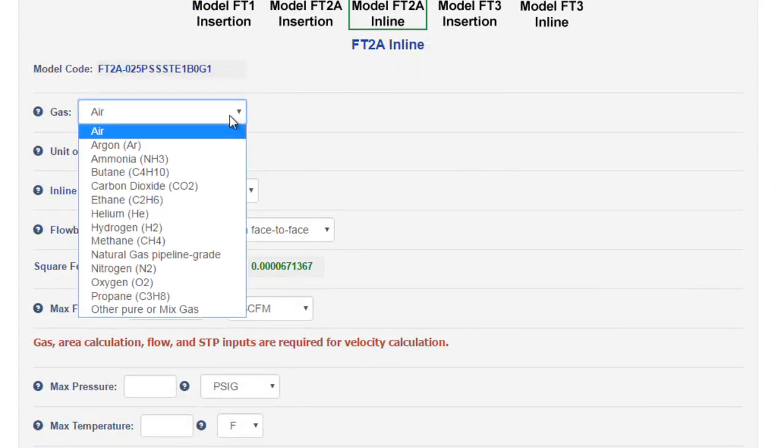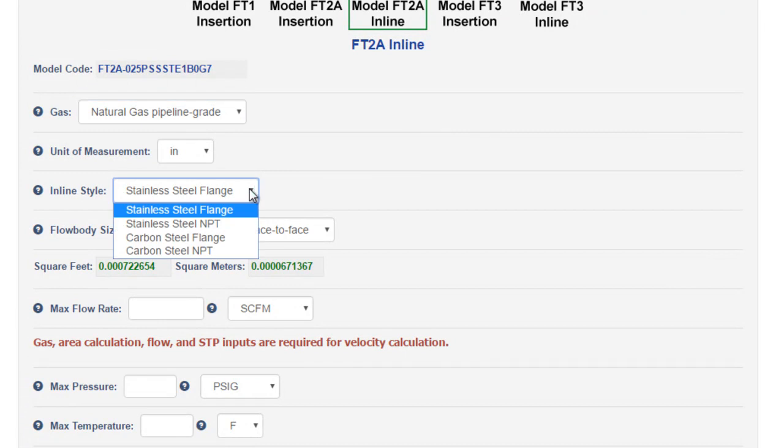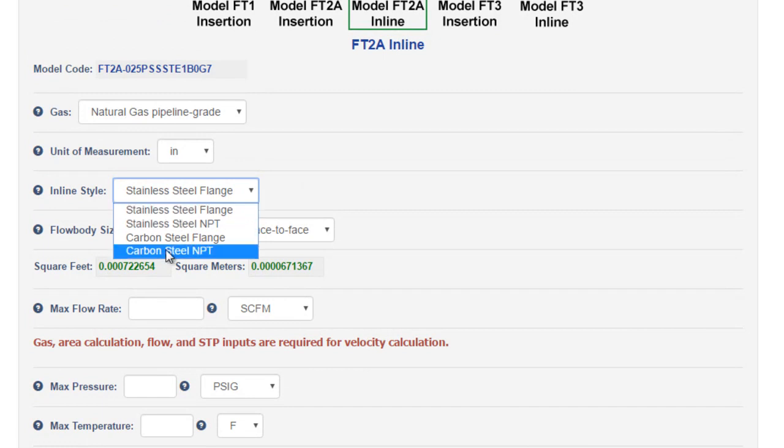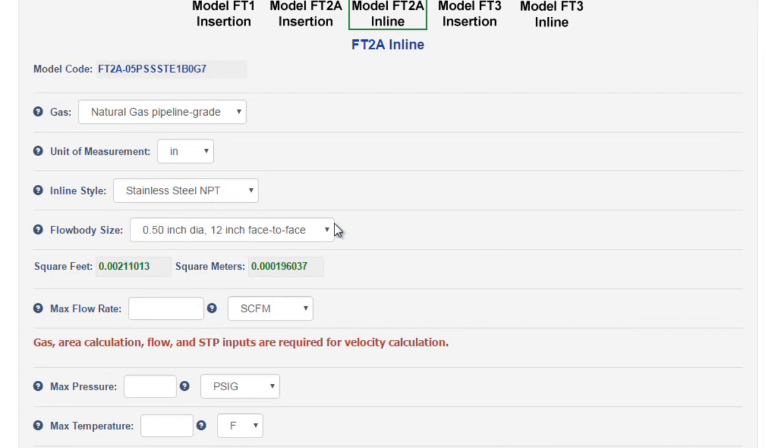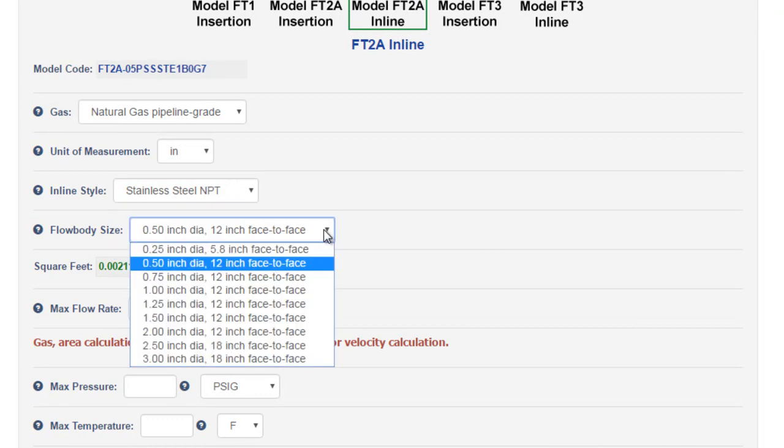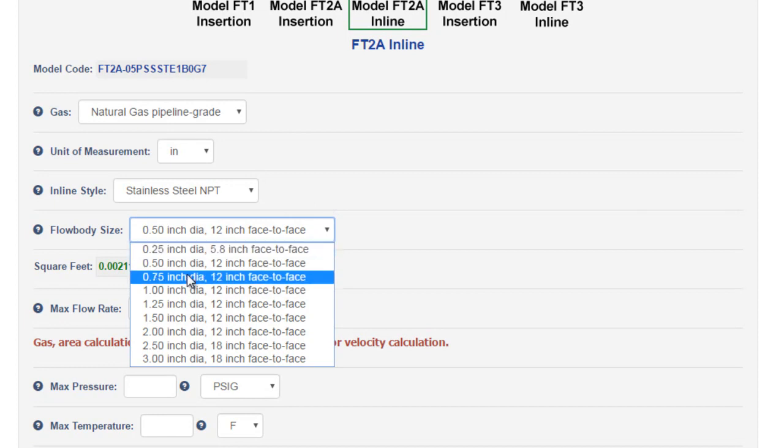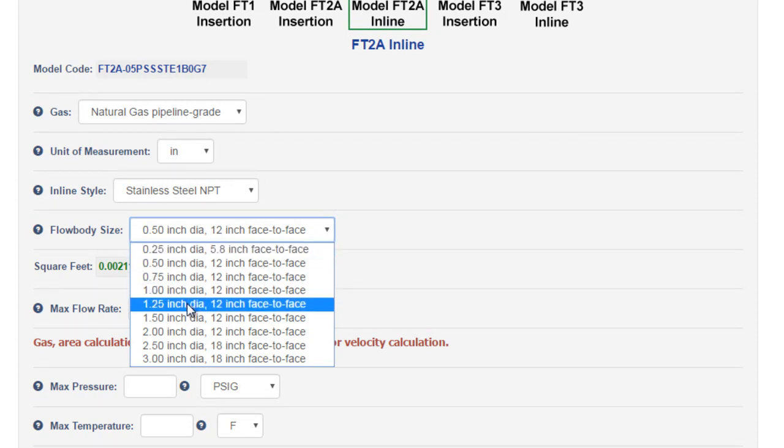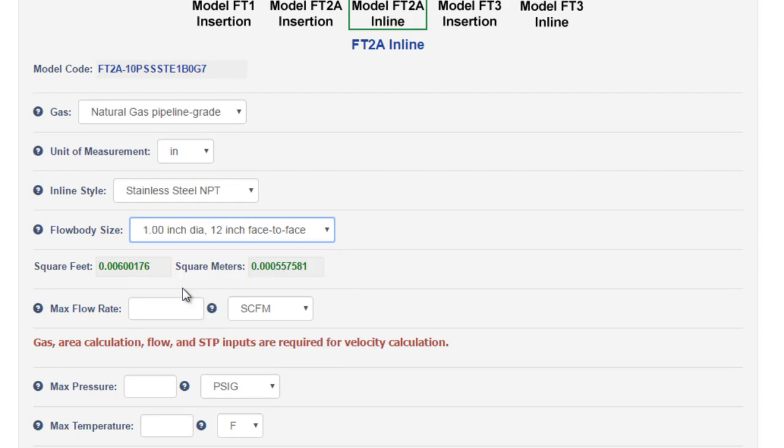This time we'll choose natural gas. We'll leave the units of measurement in inches, and then we'll choose between our process connections on the flow body. In addition to flange versus NPT, you can also choose between stainless steel and carbon steel for most pipe sizes. Let's go with stainless NPT. The flow body size is next. You'll note that the smallest pipe sizes are only available for inline meters. Quarter inch, half inch, three quarter, one inch, and one and a quarter. Let's do a one inch application.